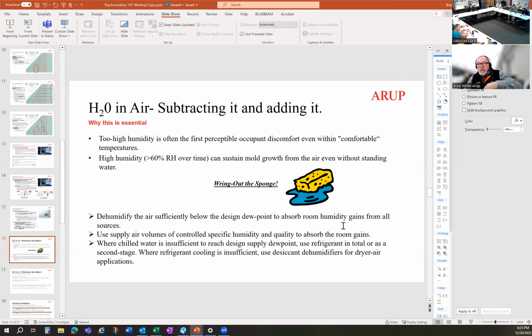Most of their units inside the buildings, in Florida in particular and in Houston, for example, are recirc units, almost like a giant fan coil unit. But they bring the outside air in, they wring it out, and that's the agent of dehumidification for that space. The recirculation unit will dehumidify, but the DOAS unit will really dry that out. It'll take it down to somewhere in the 30, 39, 40 degree dew point. And this is without desiccants. I'm just talking refrigerant process here, not desiccants. That gets down to minus 15 if you really wanted it to.